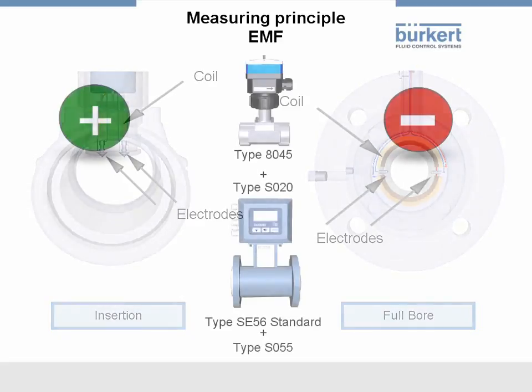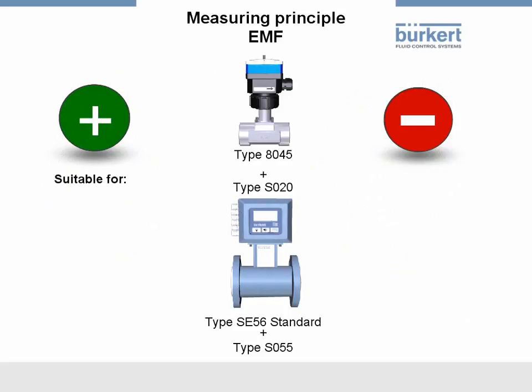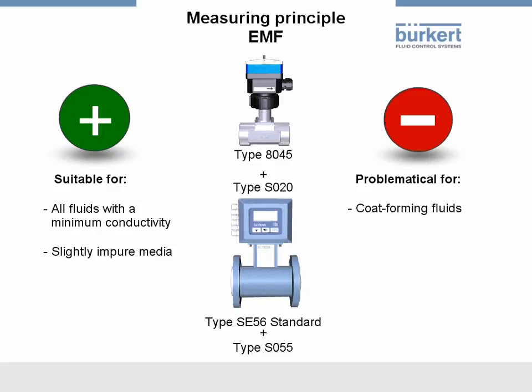An EMF is suitable for flow measurement of all fluids with a minimum conductivity. This method can also be used for slightly impure media. However, coat-forming fluids or those having an abrasive effect or contain ferromagnetic particles restrict the applications.